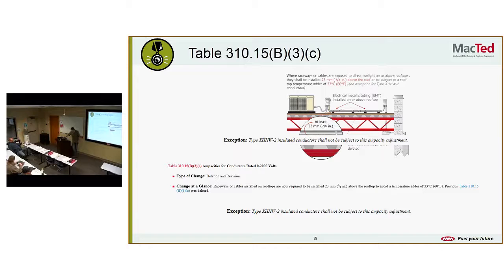Here we have ampacities for conductors rated 0 to 2,000 volts. They've deleted and revised. Raceways or cables installed on rooftops are now required to be installed, what is that, 7/8 of an inch? That's a tough one to see on my screen. 7/8 of an inch above the rooftop to avoid a temperature adder of 33 degrees Celsius or 60 degrees. So if you're going to run conduit across the roof, it needs to be installed 7/8 of an inch above the rooftop. Otherwise, you've got to add to the temperature rating. And as you should know, as you increase the temperature rating, you decrease the ampacity. So to avoid that penalty in your ampacity requirements, you need to raise it up a little bit.